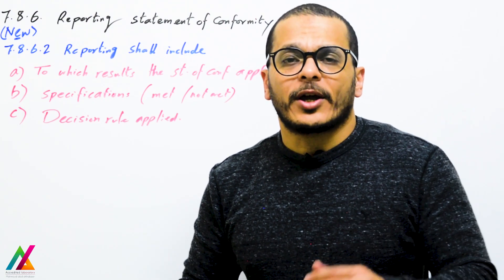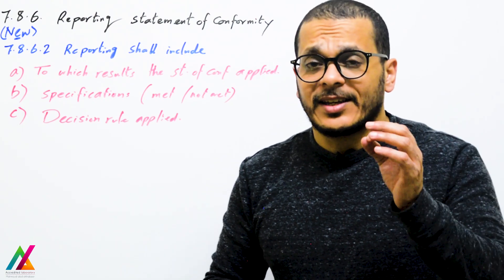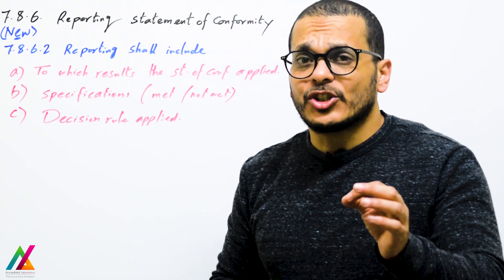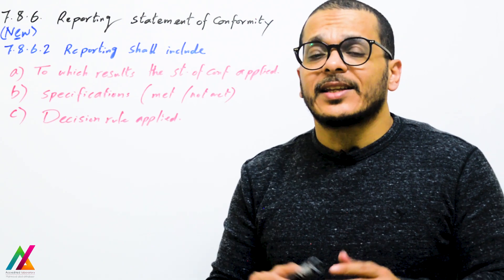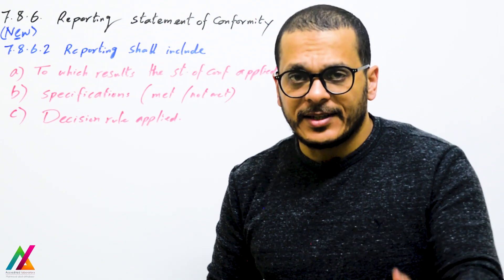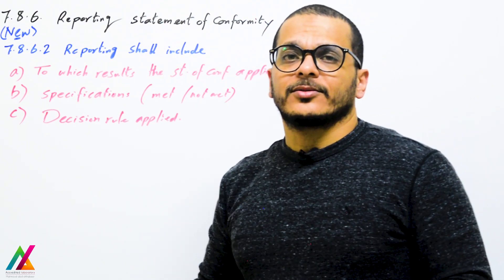The final result plus or minus measurement uncertainty, whether the result is accepted or rejected, according to which specification, standard, or guideline, the type of decision rule applied, and the associated risk — all of these shall be included. The risk will be explained in detail in the next lecture.